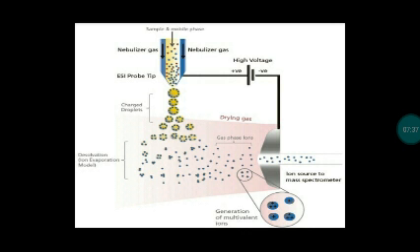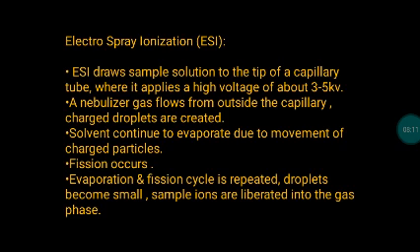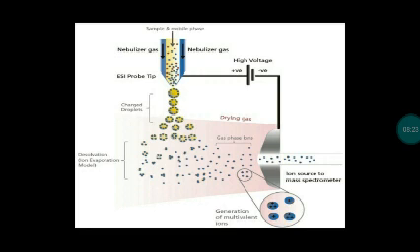The droplets are charged because high voltage potential has been applied, forming charged ions. Nebulizer gas works as a sprayer for the sample, so nebulizer flow must be maintained. As these charged particles move, the solvent continues to evaporate. As solvent evaporates due to the movement of charged particles, fission occurs. This evaporation and fission cycle is repeated, droplets become smaller, and sample ions are liberated into the gas phase. If any force inside the droplets exceeds the surface tension, this results in continuous breakdown of droplets into even smaller droplets — that is fission.